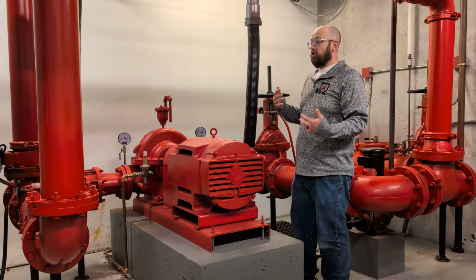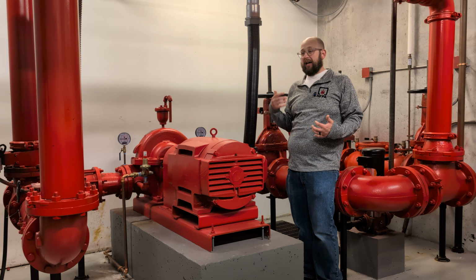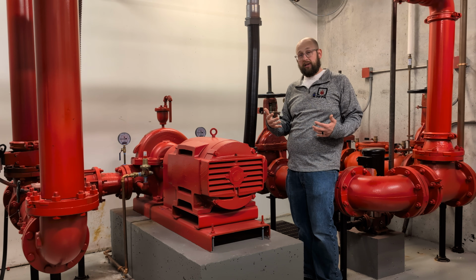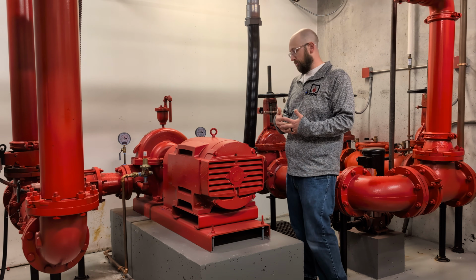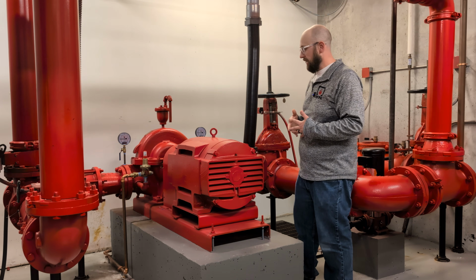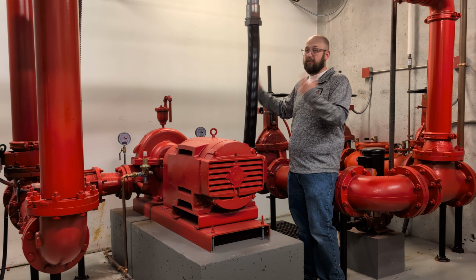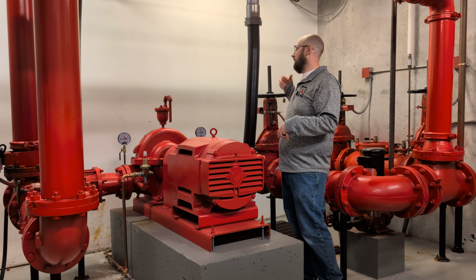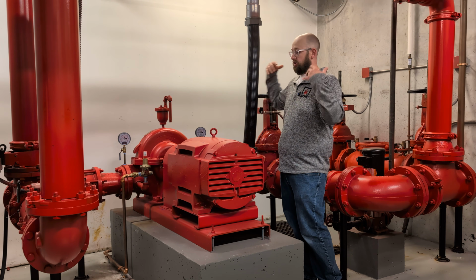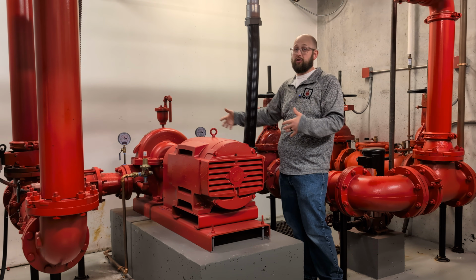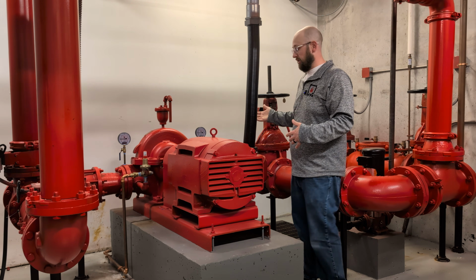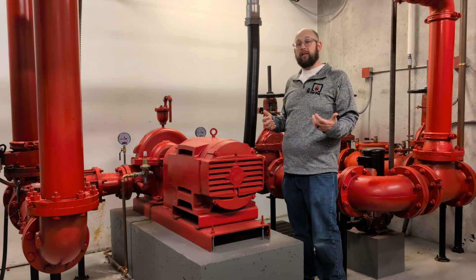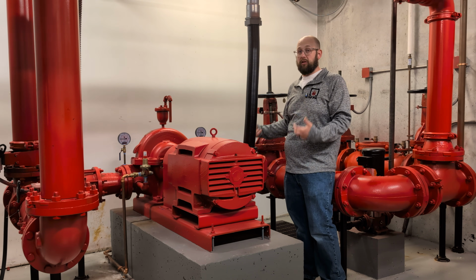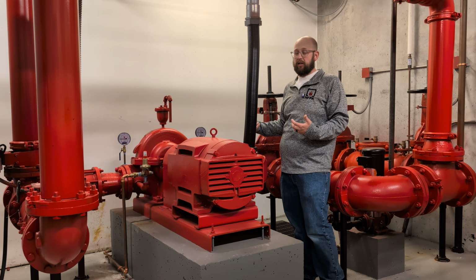And then we need to do what's called the churn test. That gets done usually monthly for most electric fire pump installations. A churn test is essentially running the fire pump for 10 minutes at no flow, just to exercise the entire fire pump and make sure everything's working. So we do that on a monthly basis. That gets increased to weekly if we're in a condition where we're really relying on this fire pump and want to make sure it remains operational.